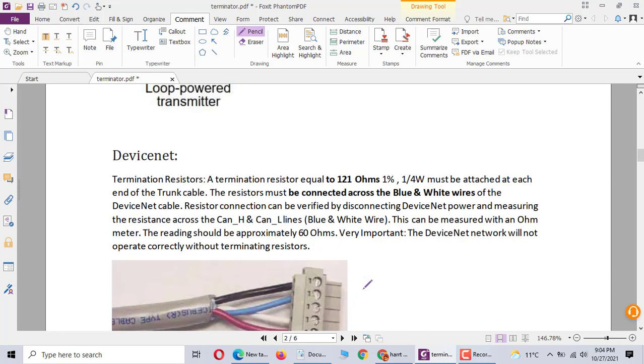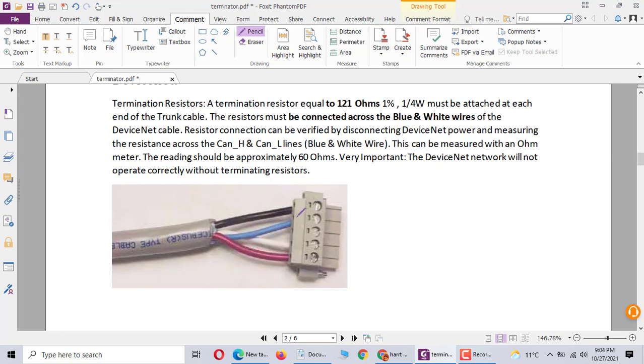In DeviceNet, you should have used 121 ohm. It's connected between the blue and white wire. Here, blue and white wire is connected, it's the termination resistor.